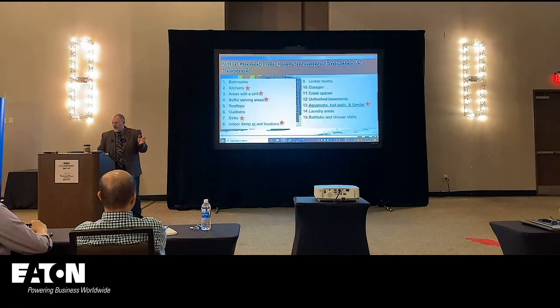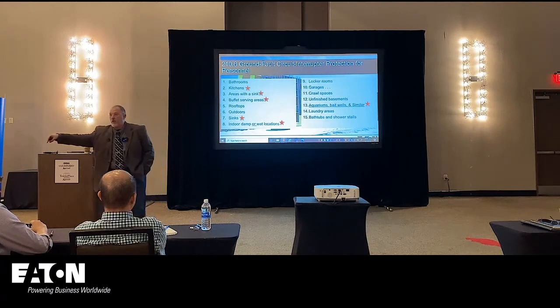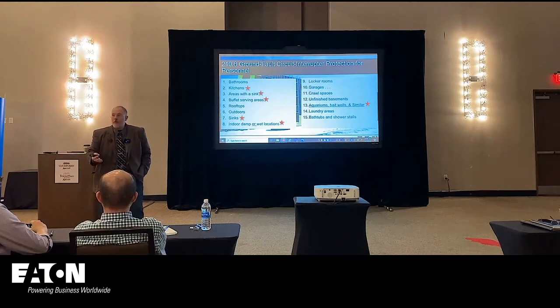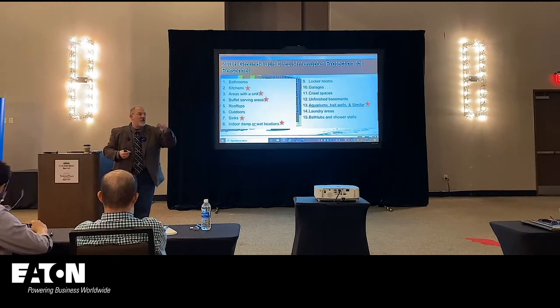210.8. Here's what we did in 210.8. I won't cover dwelling units. Other than dwelling units, kitchens: we just split out kitchens and areas with sinks. Here's what we recognized. The hazard is not the receptacle. In 210.8, we do all of our measurements off of a receptacle. Why? Because inspectors can walk into a rough-in or a final inspection, they can see the receptacles, and they can do the measurements. But we realized the hazard is not the receptacle, the hazard is the appliance. It's what's plugged into the receptacle.